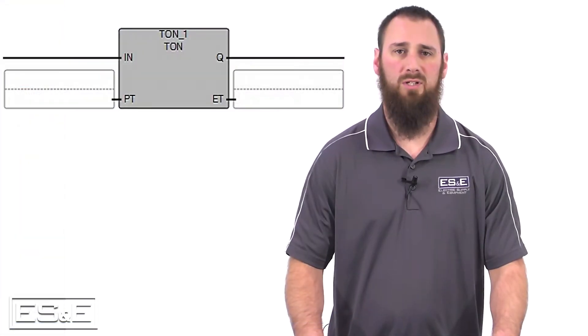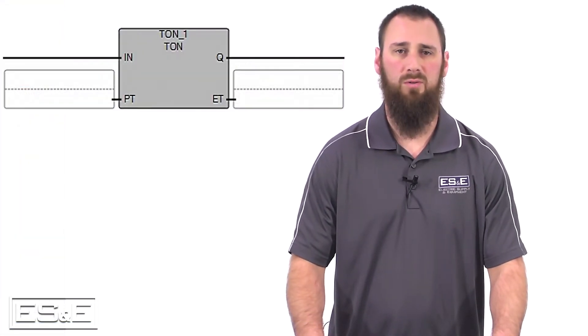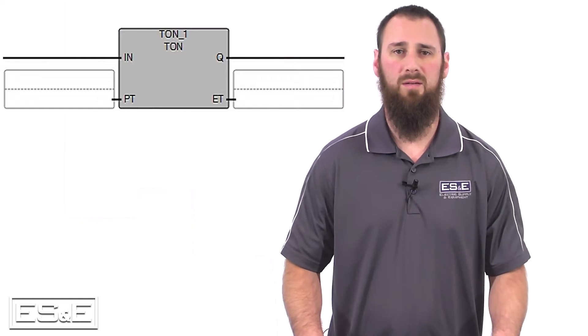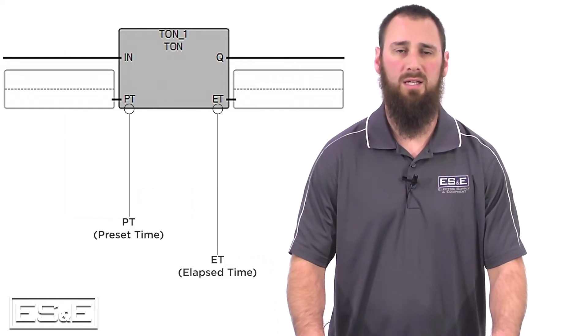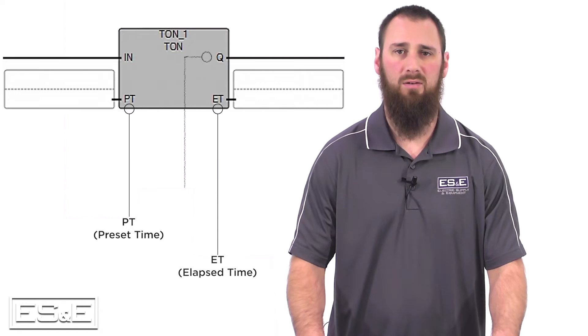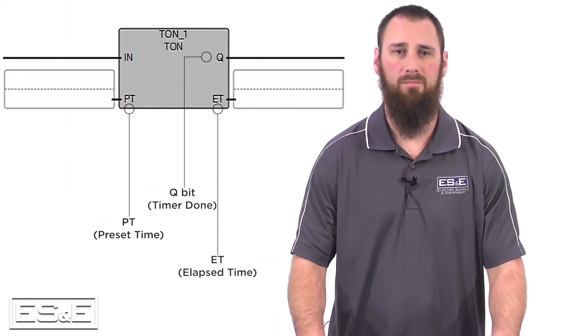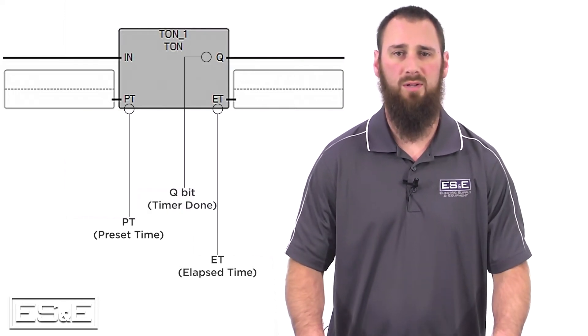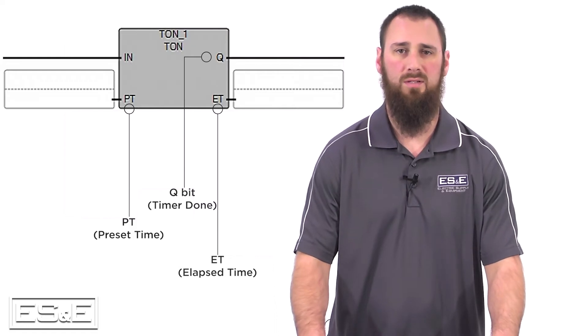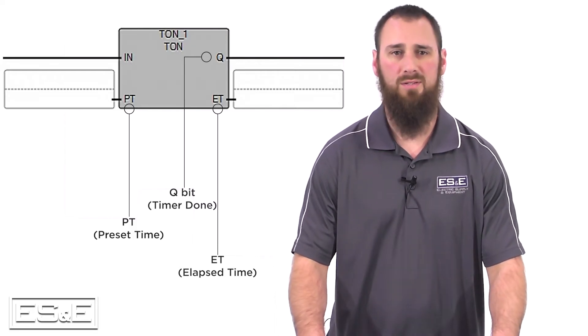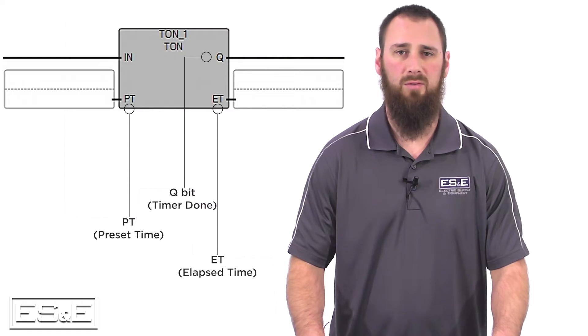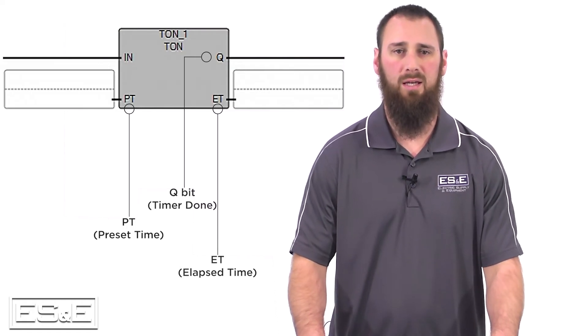The timer instruction has similar parts to what we are used to because we have the PT or preset time, the ET or elapsed time, and then you have the Q bit for timer done. The Q bit conforms to the IEC 61131 standards for PLC programming environments. Many people are used to the DN or done bit, but the DN and the Q bit are equivalent.